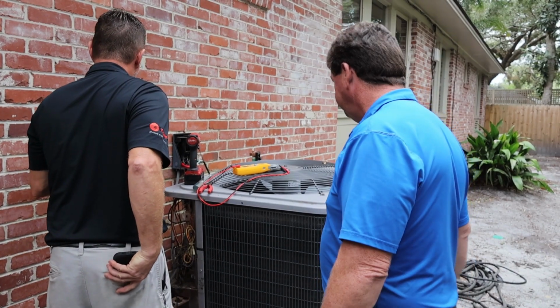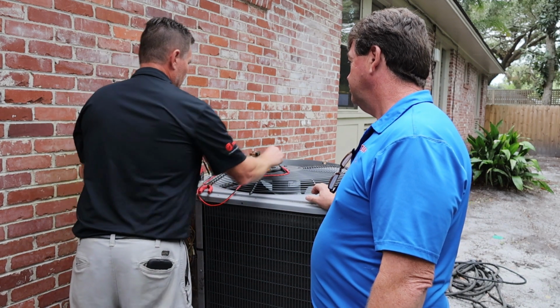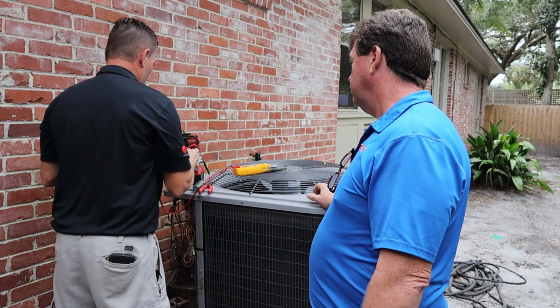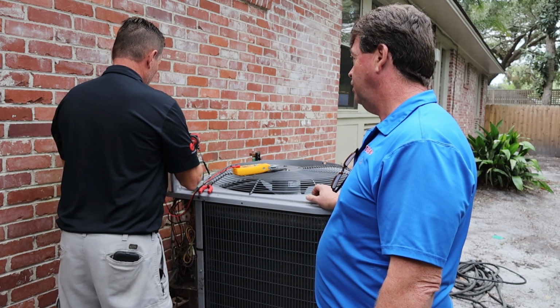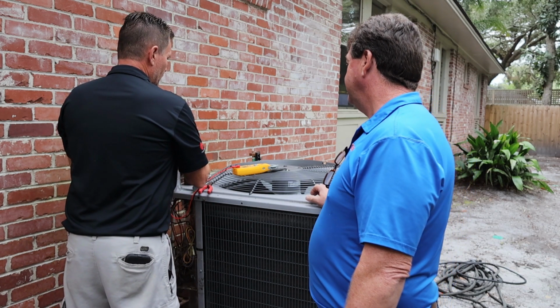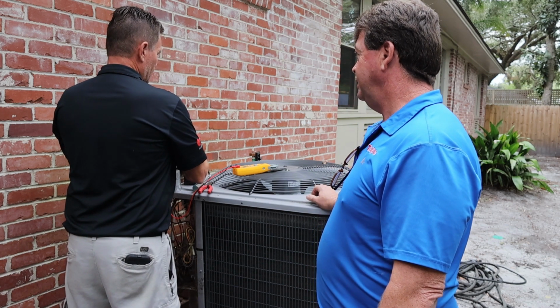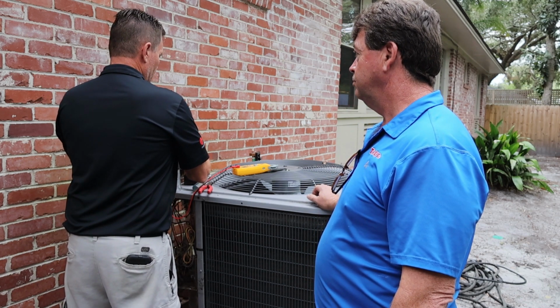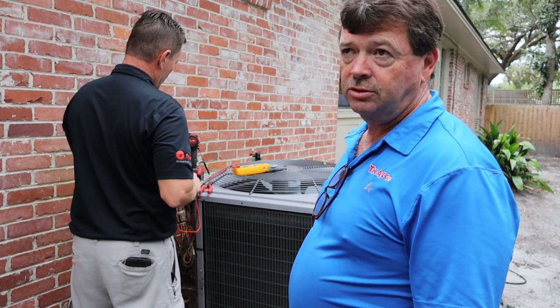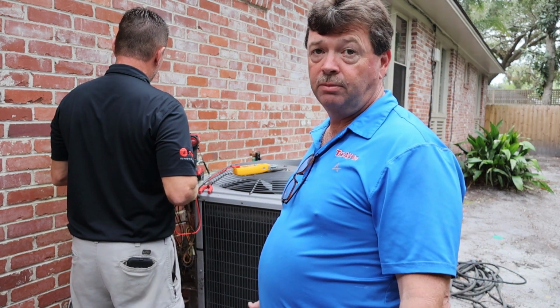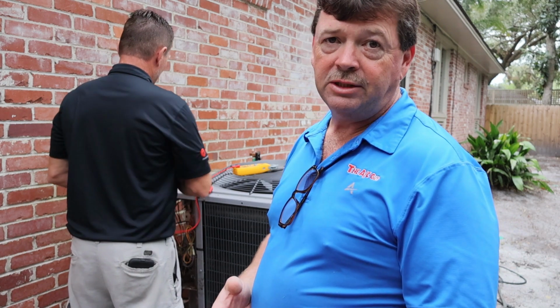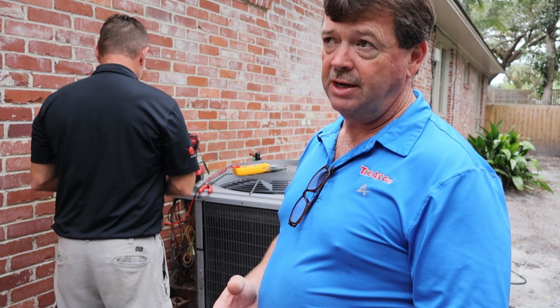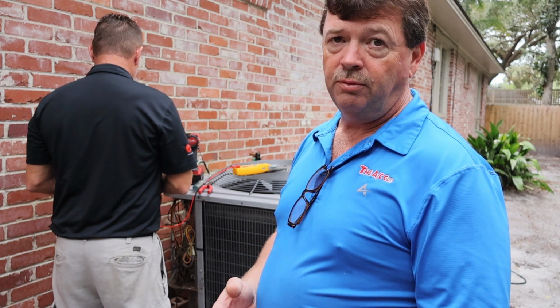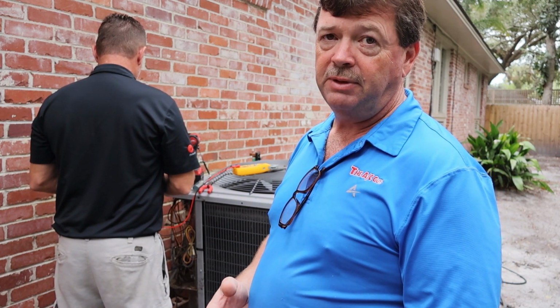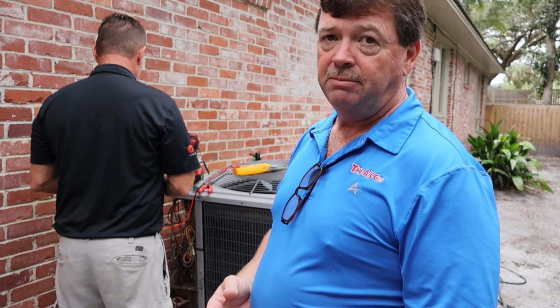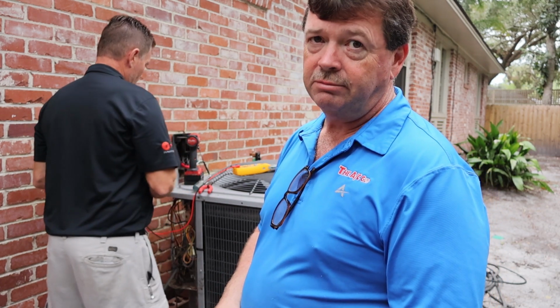I think it's all right. I mean, I would change it. So 45, it's reading 42. Yeah, so that's 3 microfarads off. Mm-hmm. What about the fan side? It's 4.9, it's good. These are what they call dual capacitors, so they work two components in the system, one being the compressor and the other the condenser fan motor. So you have to check both of them against the manufacturer's specs. If it's diminished a certain amount, it's going to have to be replaced.